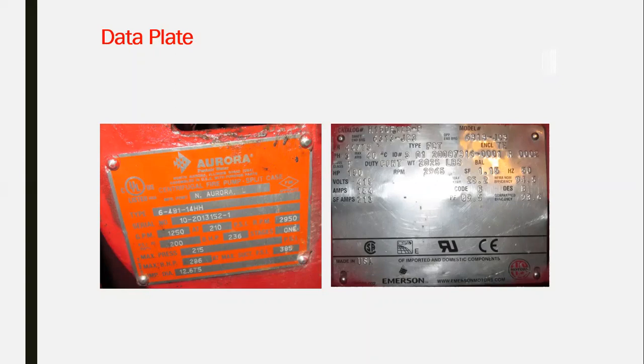The purchase order and the manufacturer clearance, it has to indicate it. When you make the selectivity, you have to indicate it. When you make a submittal for the civil defense to come for the inspection, you have to submit the data sheet and the material submitted for the fire pump, indicating clearly the serial number. It will be one of the major points QCDD will come and inspect, assuring that the serial number of the pump is matching exactly your selection, your calculation, and your material submittal and order and the test procedures. All of these documents, it has to show unique serial number for it.